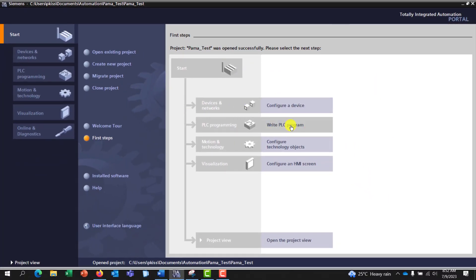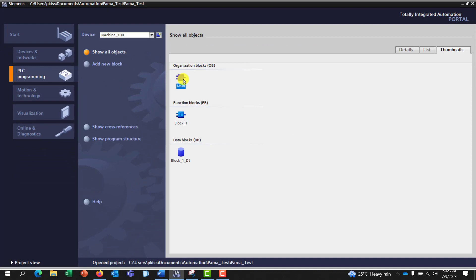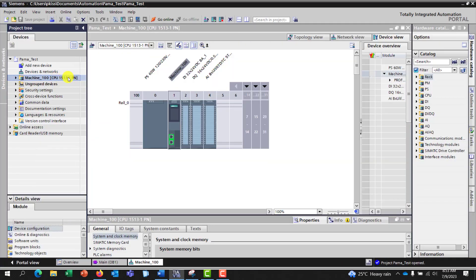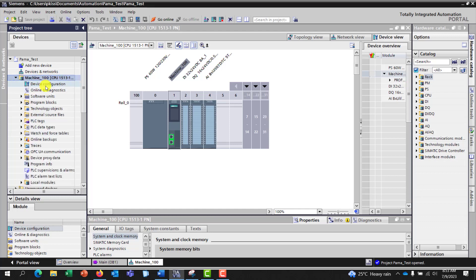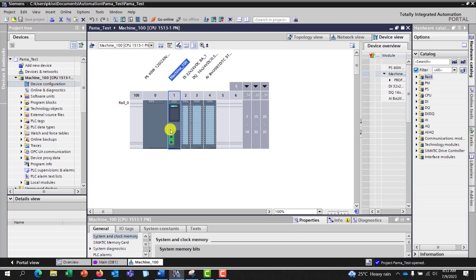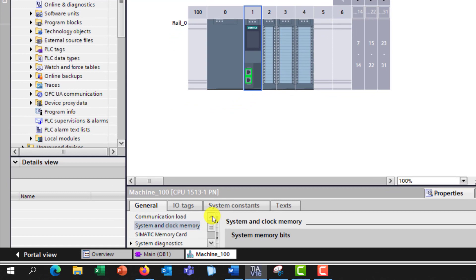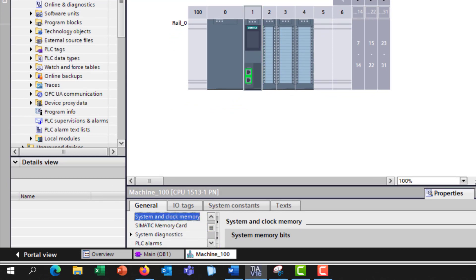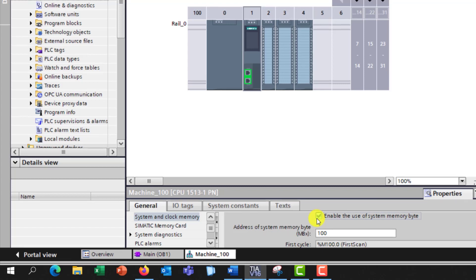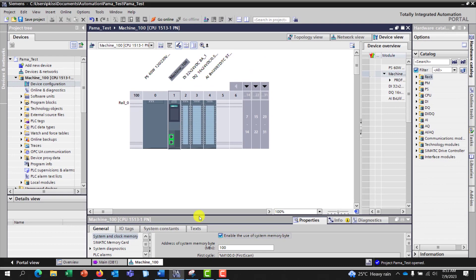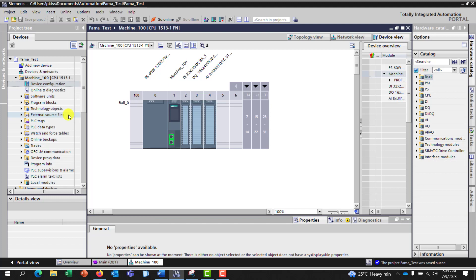To begin with, I have a simple project created in TIA Portal called Pama_Test. I double-click on it to open, then I click on the write PLC program and open the main OB block. I have my CPU, I drop the arrow and click on device configuration. If I click on the CPU, go to systems and under systems make sure to enable the use of system memory bytes.